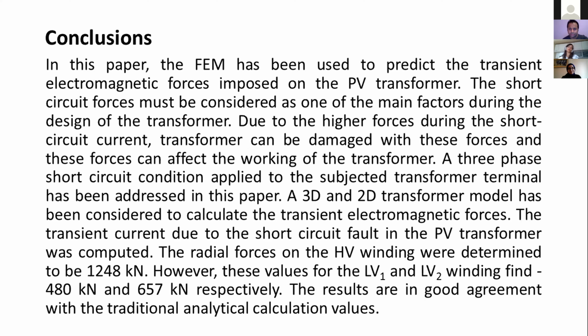In conclusion, in our paper, the FEM has been used to predict the transient electromagnetic forces imposed on the PV transformer. The short circuit forces must be considered as one of the main factors during the design of the transformer. Due to the higher forces during the short circuit current, the transformer can be damaged by these forces, and these forces can affect the working of the transformer.